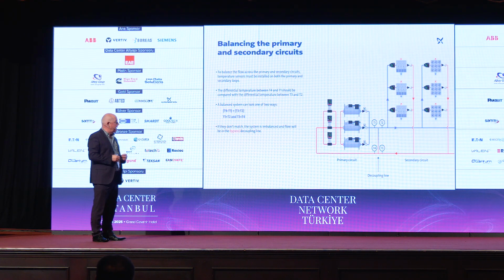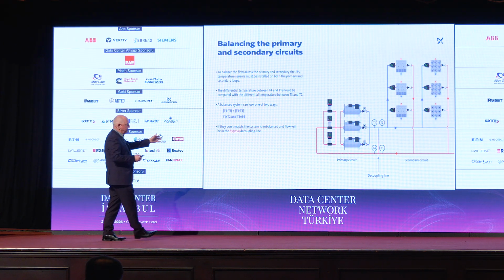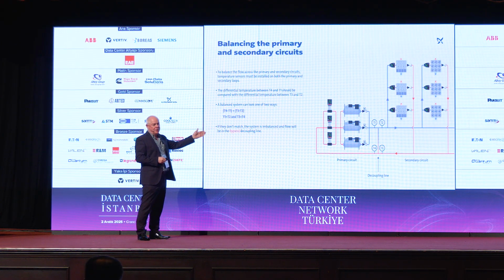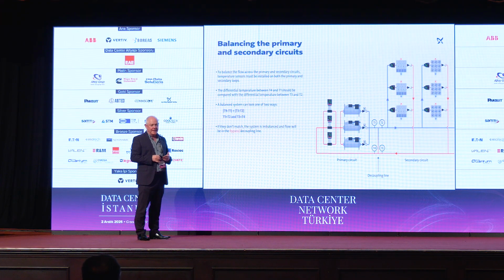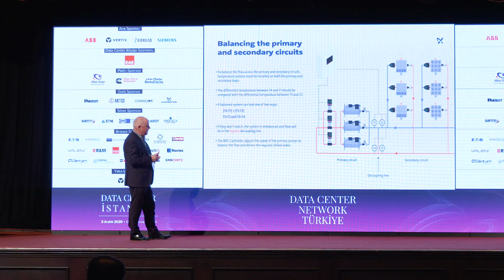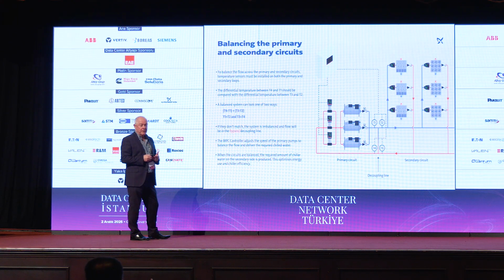We have a demo system in one of our plants in Singapore, and I've played around with it. And when we manipulate and change some of the temperatures, it comes back into sync within probably about half a minute or so. So it's reacting pretty quickly. And as I said, they're standard temperature sensors, standard controls, standard pumps. Everything is standard in this system. It's just organized in a slightly different way. So the idea is we have no flow in the bypass or the decoupling line. And that optimizes the whole energy consumption on the system.